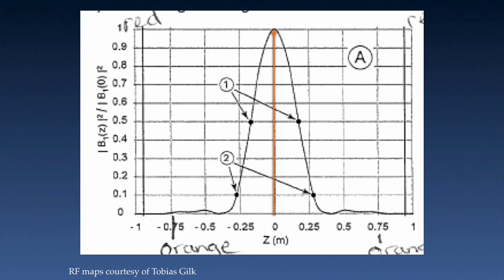The vertical axis of the graph is the percent of RF power, so anything located at isocenter would be receiving 100% of the RF power. You can also tell by the map that this coil is approximately 0.6 meters or 60 centimeters in length. If an item was located 0.25 meters or 25 centimeters from isocenter, it would be receiving approximately 20% of the maximum RF power. If it were located here, it would be receiving approximately 10% of the RF power.